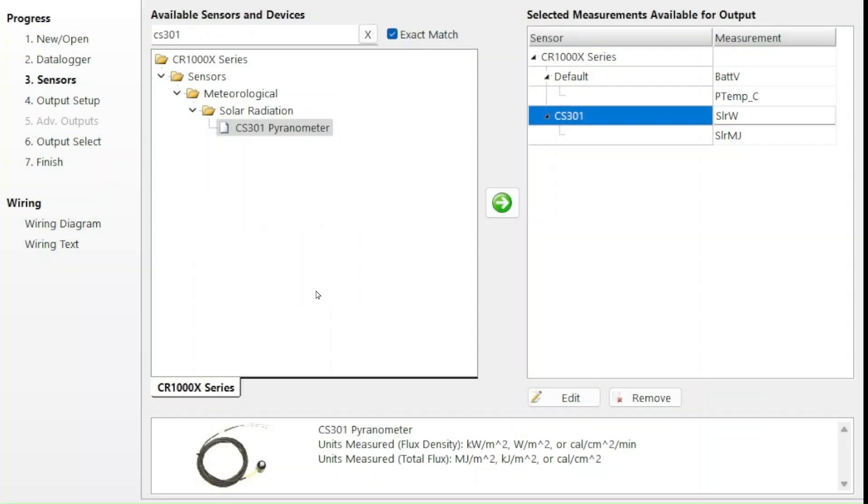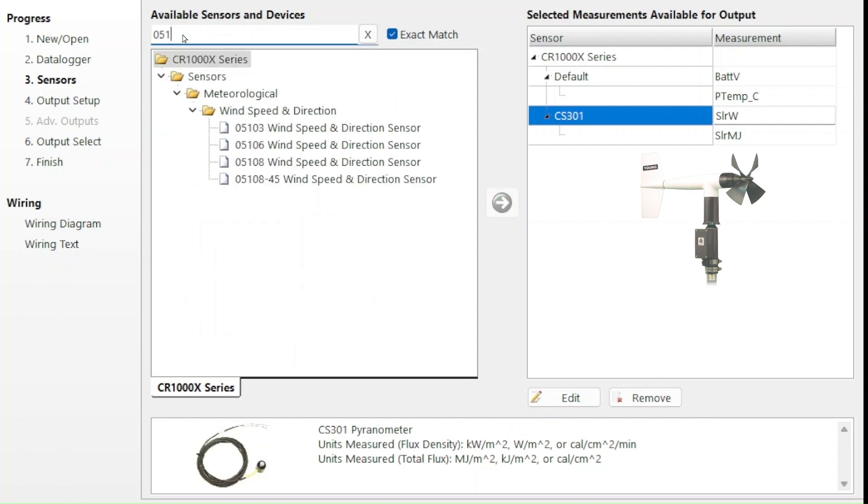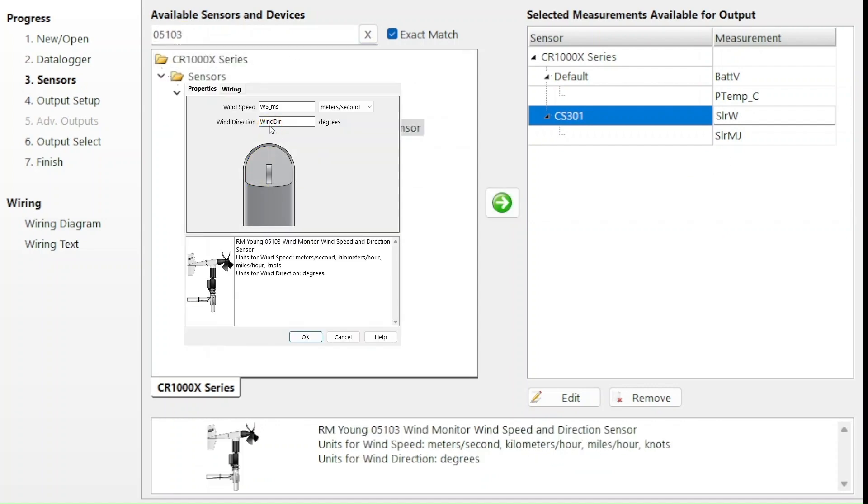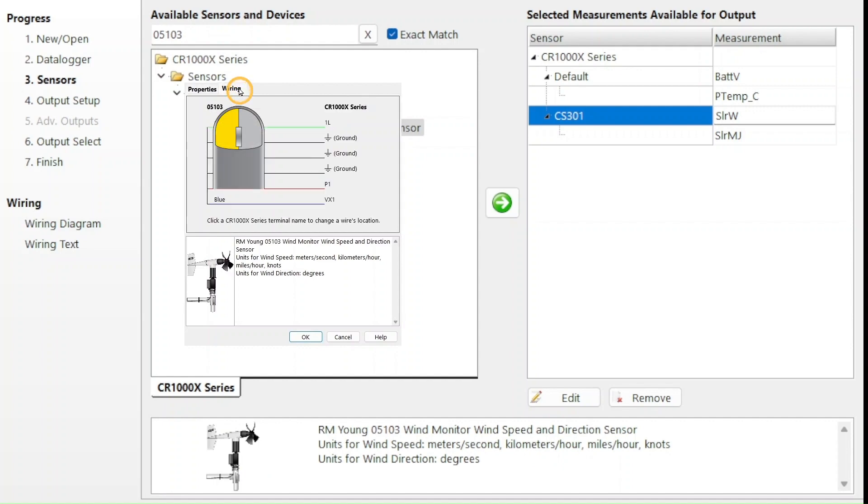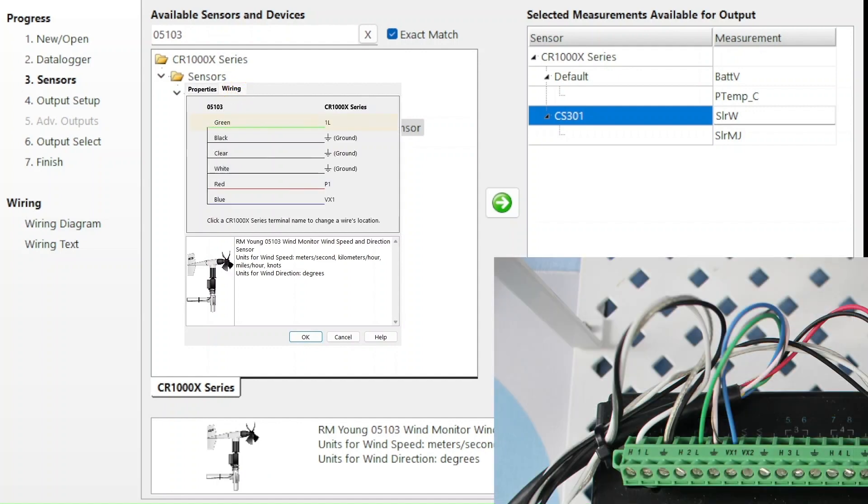Now I will add the 05103 wind monitor. I search for that and double click it to open the window. The wiring tab shows me a green wire going to channel 1L, but my photo shows the green wire going to channel 2L.